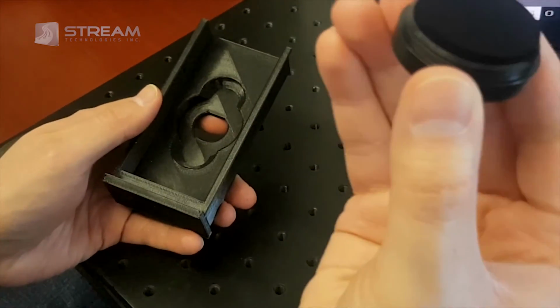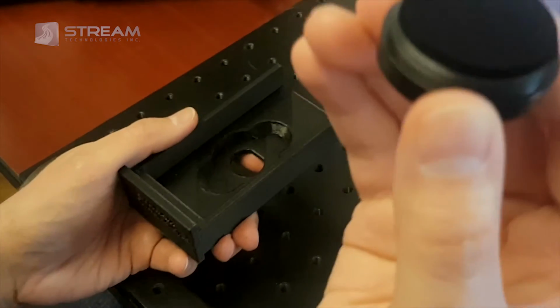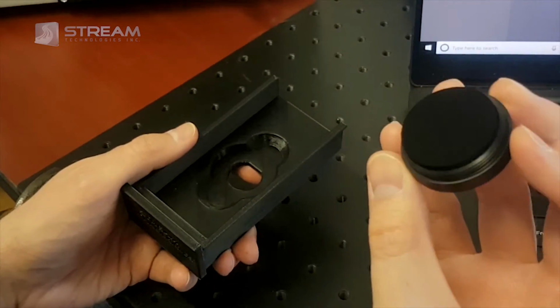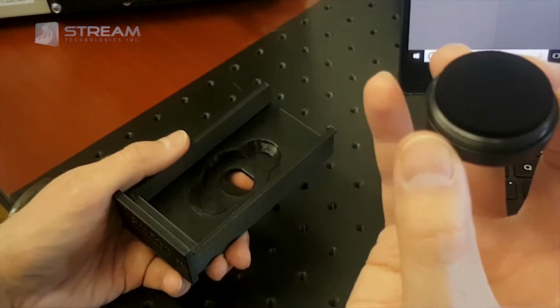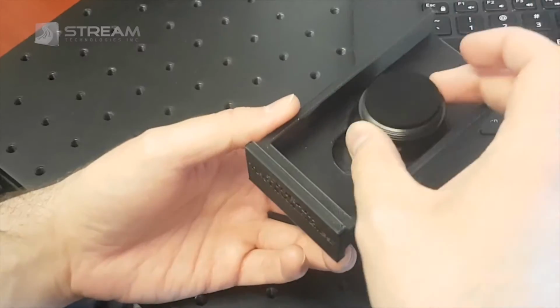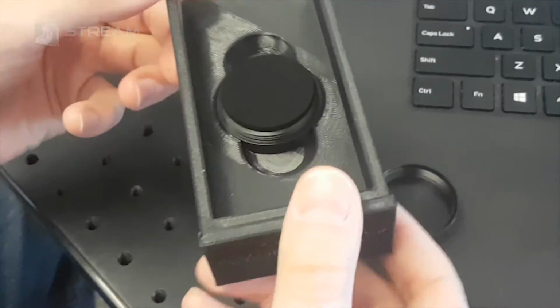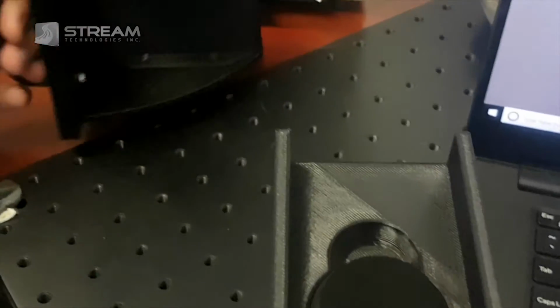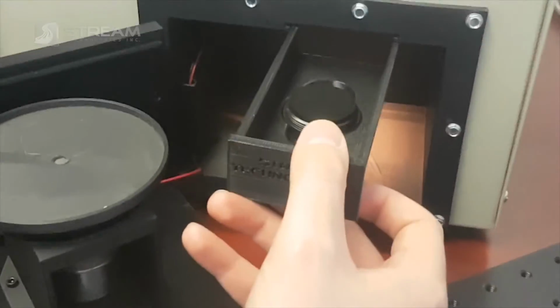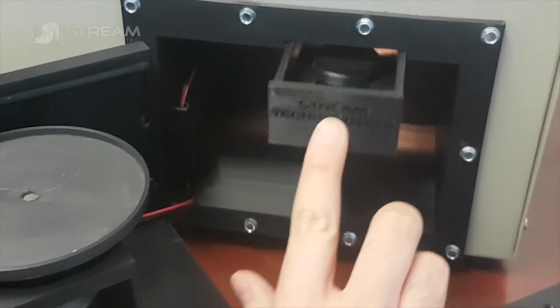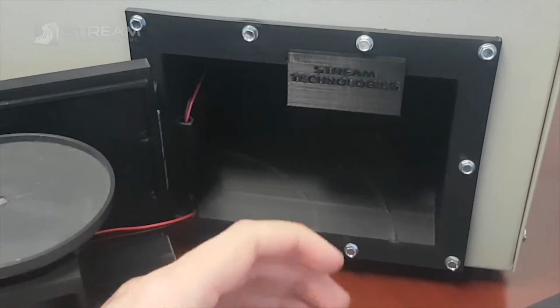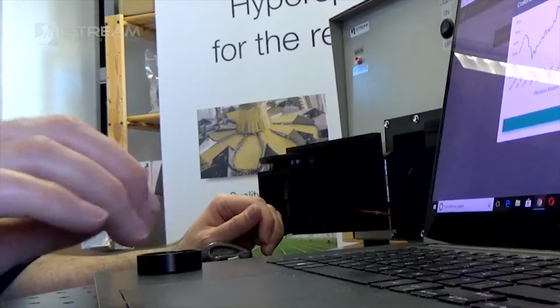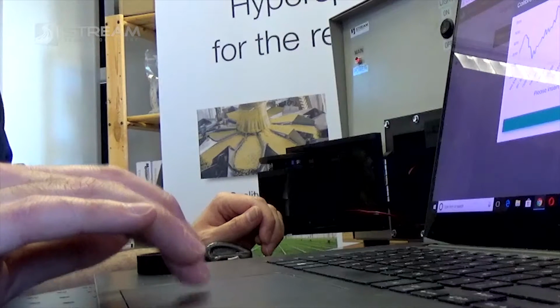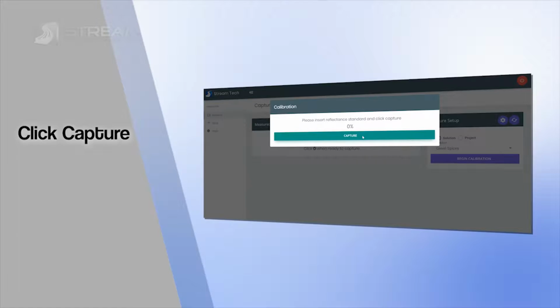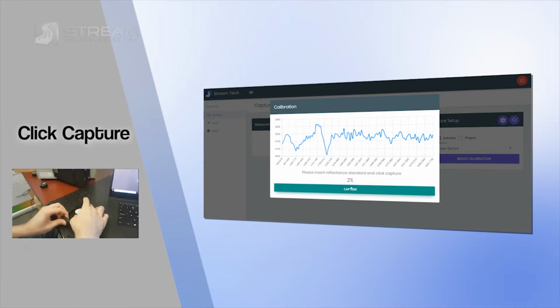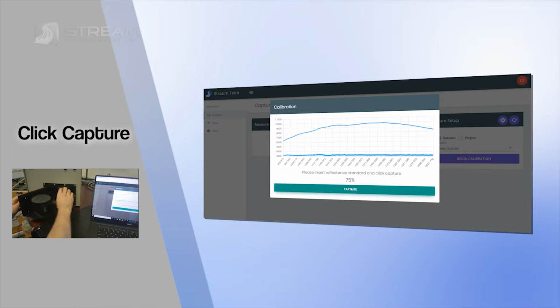If you get some dust on them, you can clean them off with a bit of dry air. Don't blow on them because that'll just get moisture on them. There's a little slot that accommodates these. You just put that into the drawer like so, and then open the chamber, and again put it into the slot. Push it all the way back. So once that's in there, you can go ahead and hit capture on the calibration window. You want to go through all the remaining standards in the same manner.